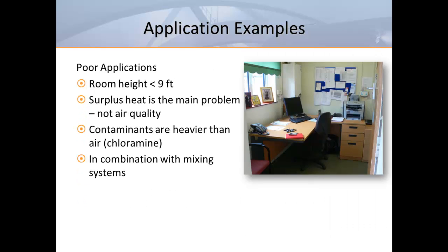Now let's look at the places where we wouldn't recommend using displacement. Since displacement works best in large open spaces, confined spaces with low ceilings don't allow us to take advantage of stratification — these spaces are best handled with mixed air systems. If the heat loads are greater than 30 BTUs per hour per square foot, we would likely create a drafty environment if we tried to use displacement.